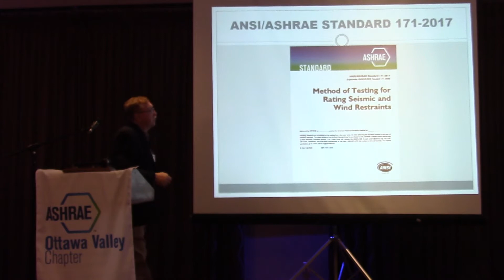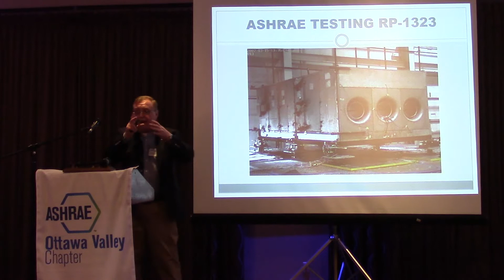Next I've got 3 videos. These are shaker table tests of 2 pieces of equipment for seismic certification for California hospitals. This is an ASHRAE test. We wanted to see what was the best seismic restraint we could come up with, and there were 3 things we looked at: how thick the rubber was, how hard the rubber was, and the air gap in the rubber, remember the angle I showed you?